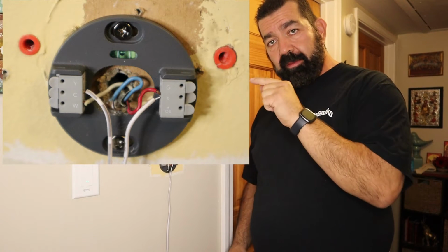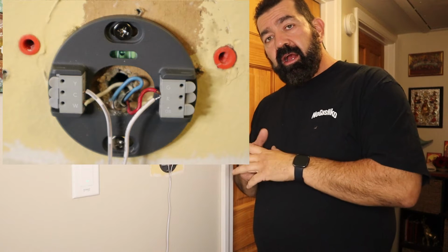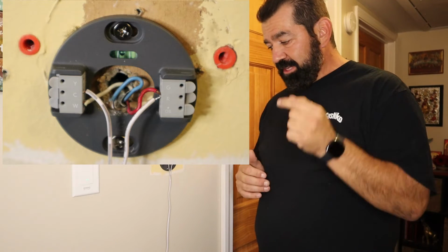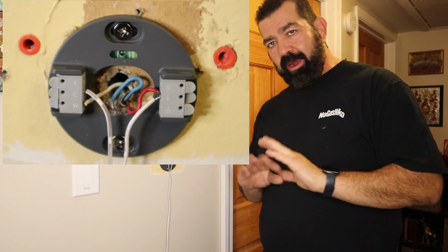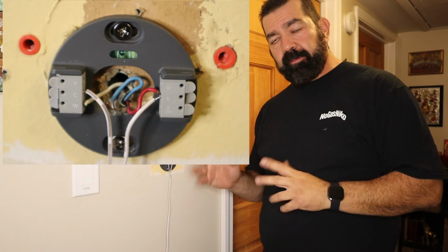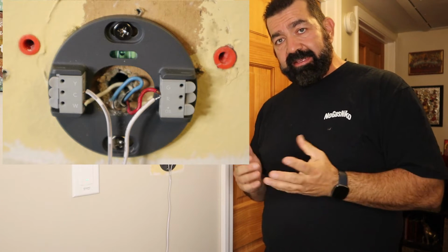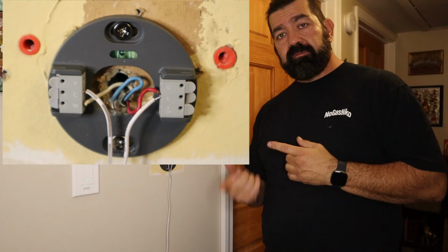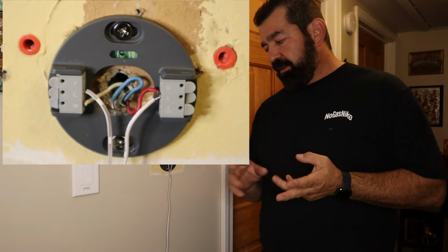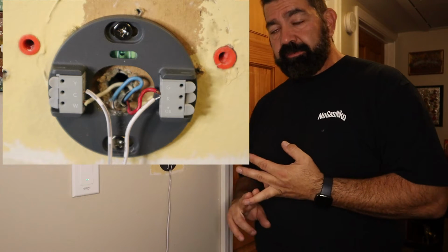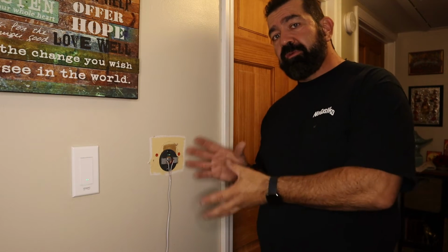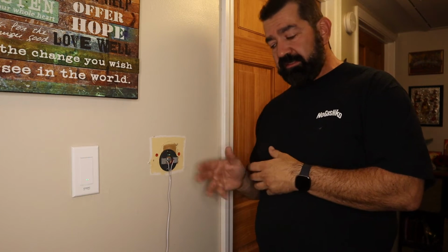The blue wire in the back there, put an arrow to it. That's not connected to anything, it's actually stuffed back in there. Even though you can see the blue wire, it's not landed on any of these terminals. I'm not using it because I don't have cooling, I don't have a fan. That wire is not needed for my system. Again, this is how you install for heating only systems.